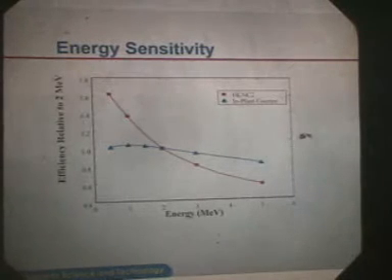But the energy sensitivity is another one, where if you change the energy spectrum, if you cool the neutron spectrum because of a few collisions before it gets detected, it changes the effective efficiency because the detector is designed for a certain energy neutron. If you change that, the efficiency shifts. But because the multiplicity detectors have many, many rings of detectors, they tend to have a much broader and flatter energy sensitivity than coincidence counters, so this effect of matrices is actually better for neutron multiplicity counters in addition. All right.